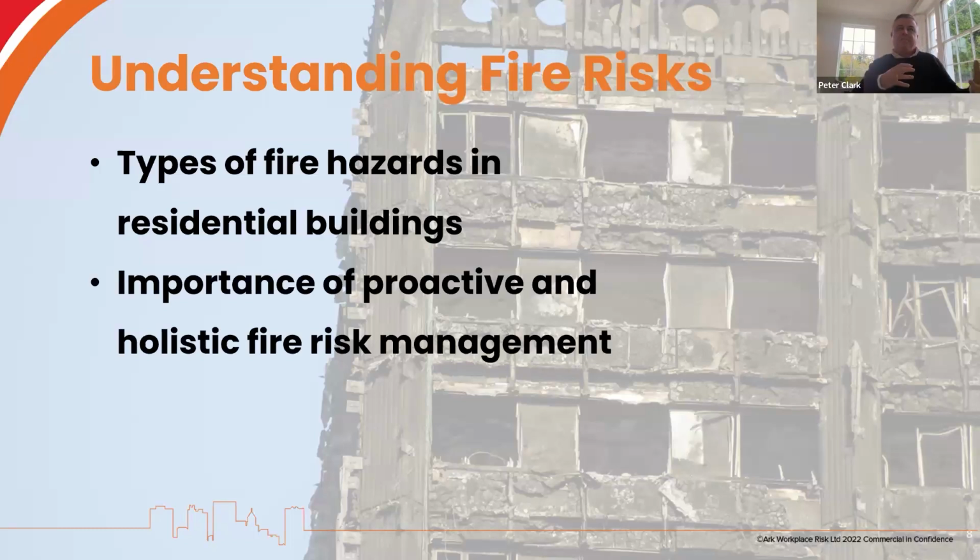So go back to that two-body problem that I talked about there, where the fire and rescue service might be saying a fire risk assessment is actually okay. That fire risk assessment could be what we commonly know as a Type 1, where when we're conducting that type of risk assessment, we're looking non-intrusively at the common parts of a building. That's all the RRO tells us to do. Whereas the Building Safety Act, for a higher risk building, tells us to do something different. So Section 156 of the Act goes a little bit further.